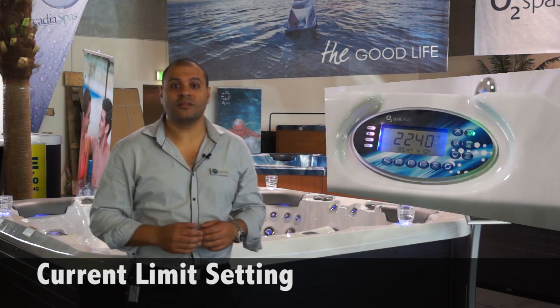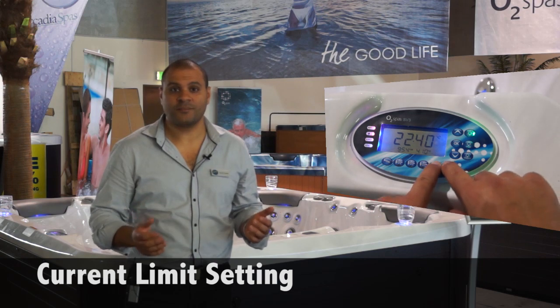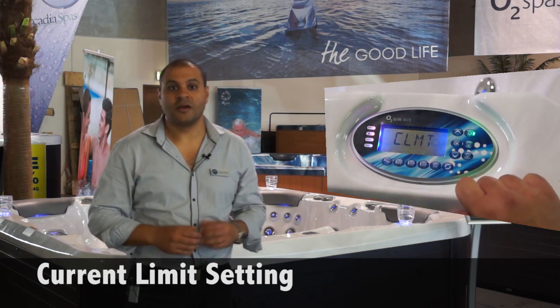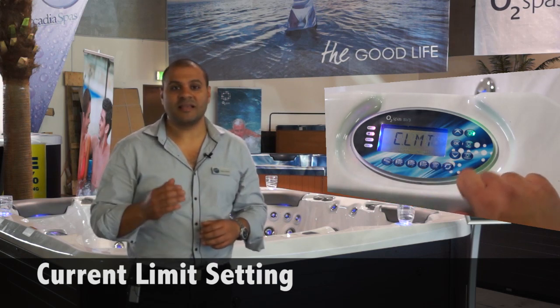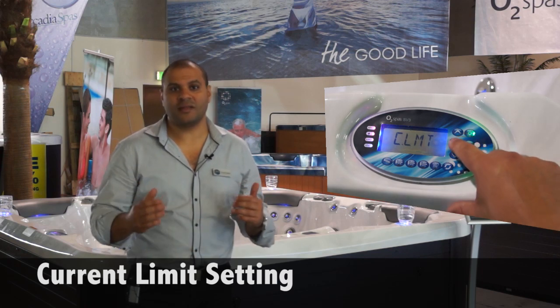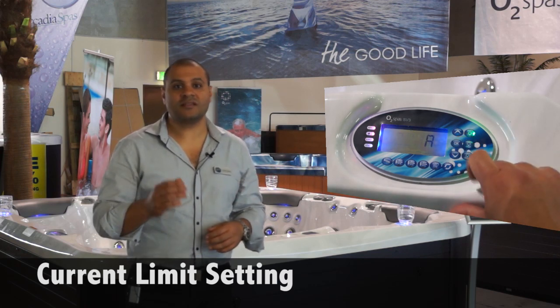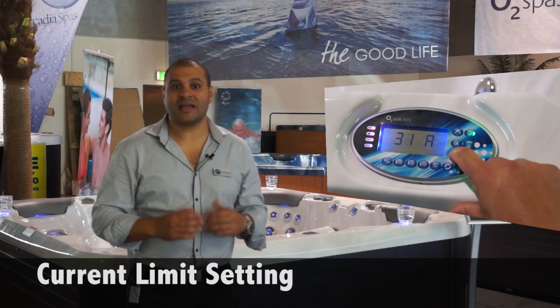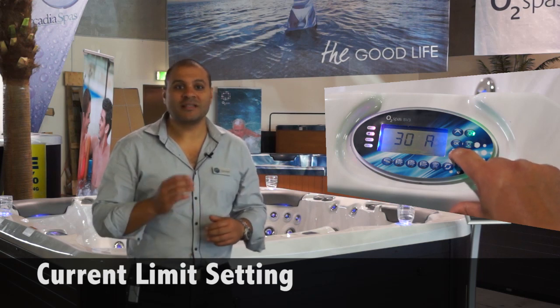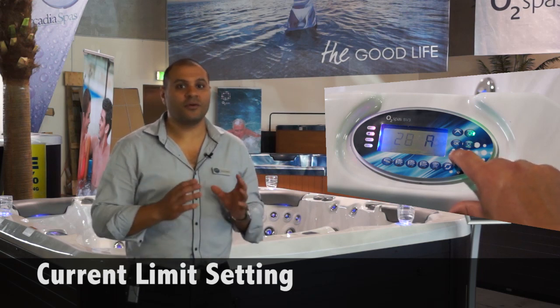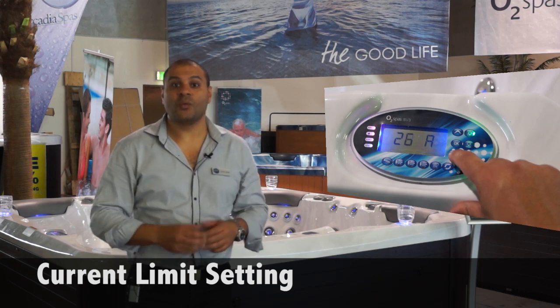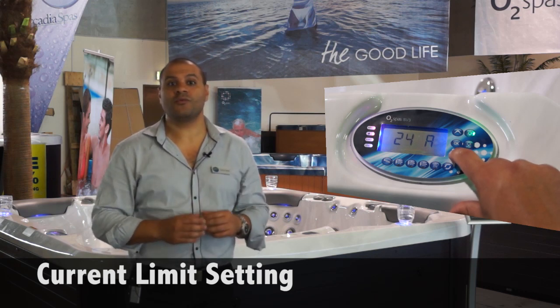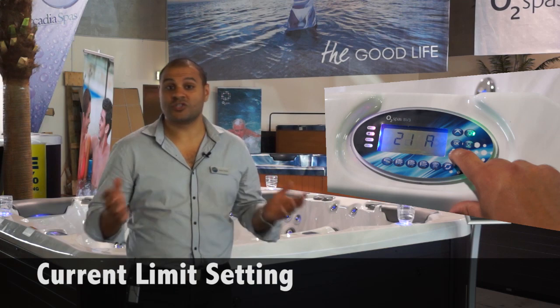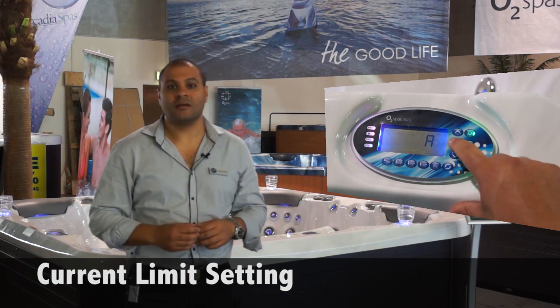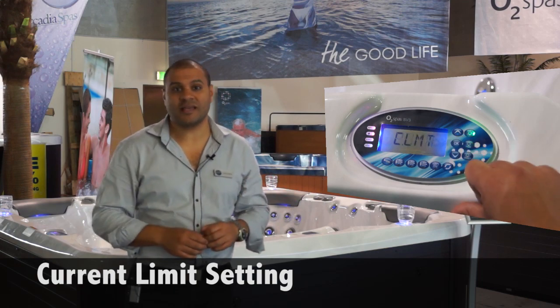By pressing and holding the blower and clean cycle buttons together, a service menu appears. The first choice on the menu is CLMT. This is the current limit settings. When you see this, release the blower and clean buttons and press the OK button. You can see in this example that the default limit is 32 amps. We can now press the down button until we reach our desired current limit, which is 24 amps, then press OK. The current is now set to 24 amps.